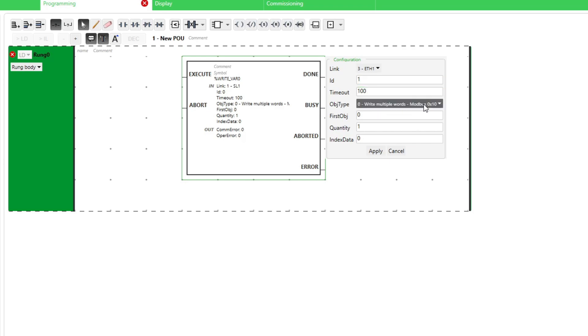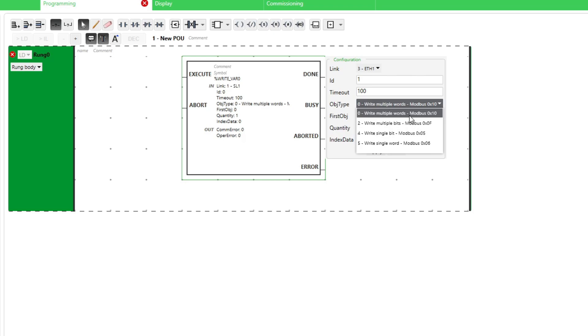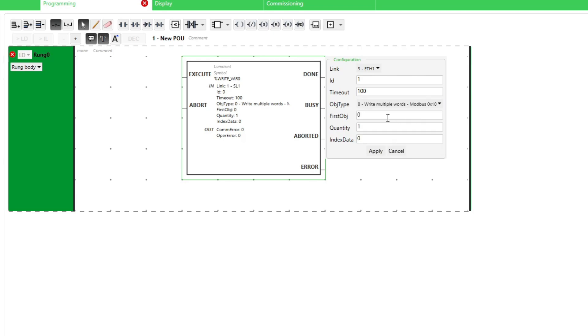Object type I will also keep as it is, since I want to write multiple words to my Siemens PLC. First object is the first Modbus holding register address it should write to, and quantity is for how many addresses it should write. I want to start from the first address and write 10.